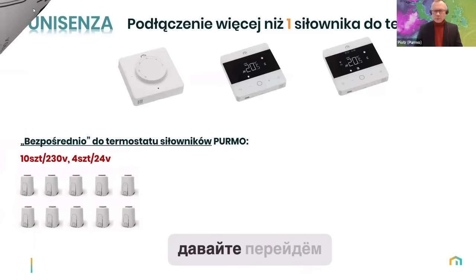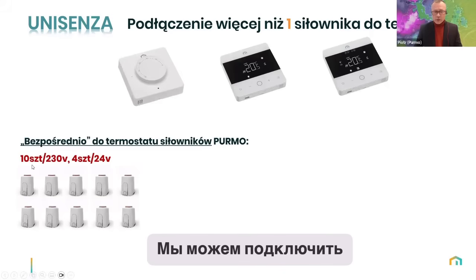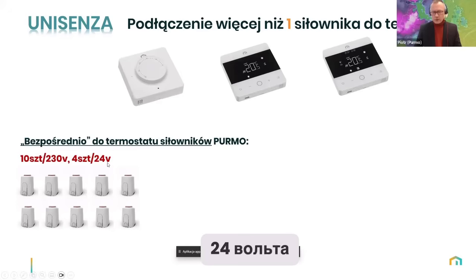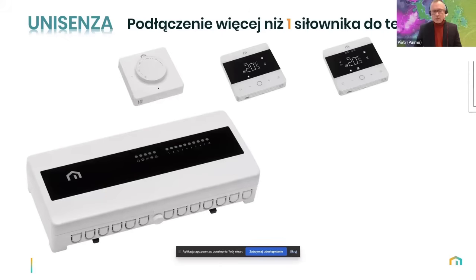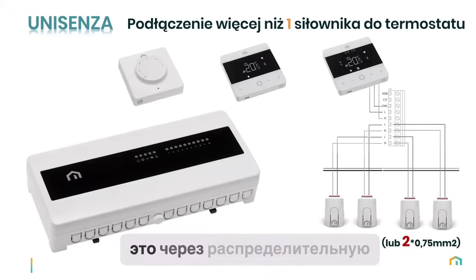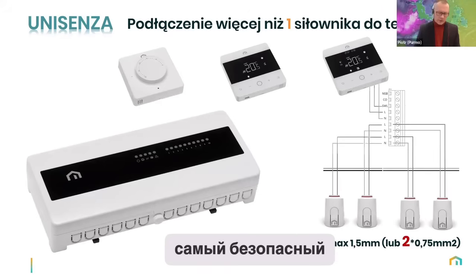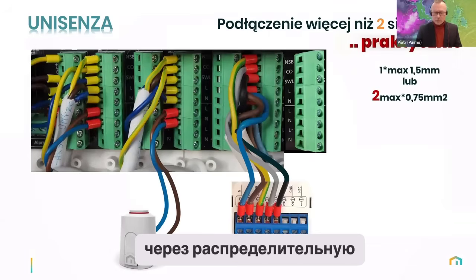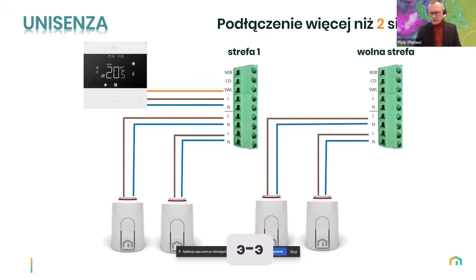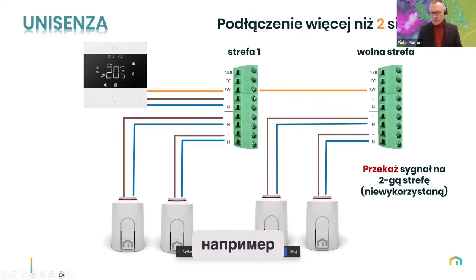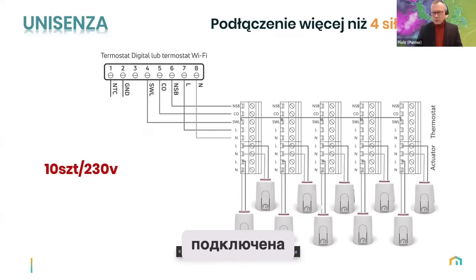So let's jump to the other. We can connect quite a lot of actuators directly to the one thermostat: 10 actuators at 230 volt, or 4 actuators at 24 volts. Of course, we always prefer to make it by wiring box, because this is the safest way. By wiring box we can make different approaches. For instance, if we have 2 zones, we can use it, and then everything is connected by wiring box, which is simply safer.